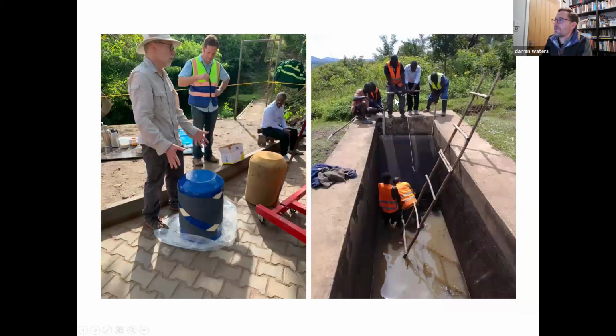There's a picture of that now. On the left, Jonathan's giving a bit of a toolbox talk at the beginning of the day as to what we were going to do. You can see the old pig, just the foam pig there, and this one is the same, but it's covered with a very durable, rubbery plastic with a sort of carborundum sandpaper type finish. That was deliberately to knock off some of the nodules Jonathan was talking about on the inside of the pipe, where the corrosion was happening underneath. So knocking off the top would slow down the corrosion anyway, where the pits were.